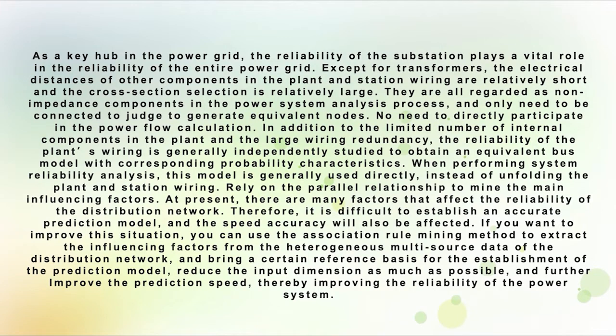No need to directly participate in the power flow calculation. In addition to the limited number of internal components in the plant and the larger wiring, the reliability of the plant's wiring is generally independently studied to obtain an equivalent bus model with corresponding probability characteristics. When performing system reliability analysis, the model is generally used directly, instead of unfolding the plant and station wiring.